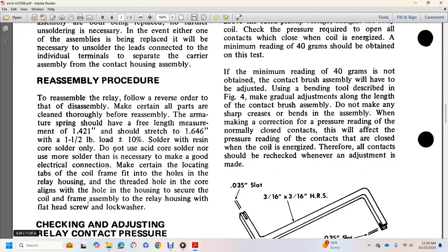Make certain all of the parts are cleaned thoroughly before reassembly. The armature spring should have a free length of 1.421 thousandths of an inch, stretching to 1.646 inches at 1.5 pounds load, plus or minus 10%. Soldering: use resin core solder only.